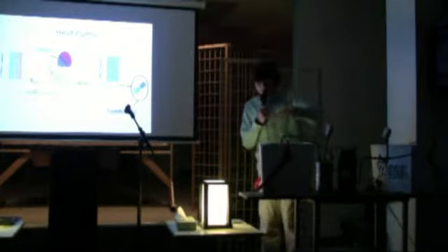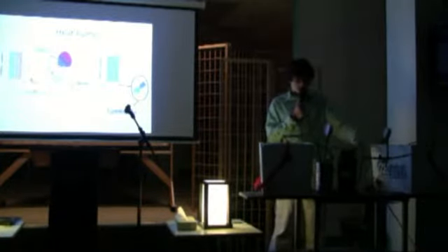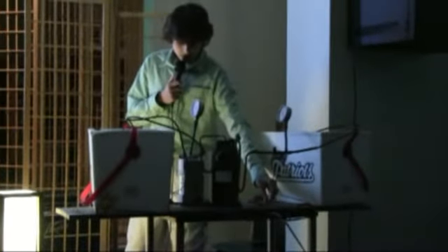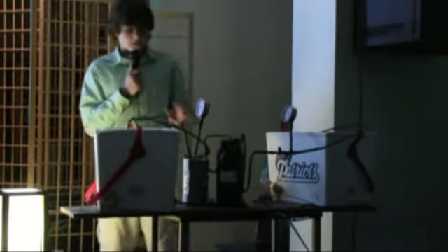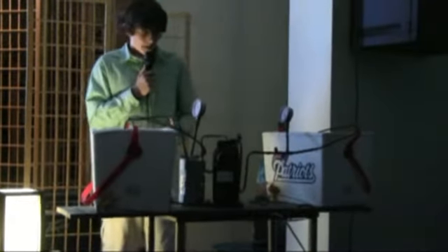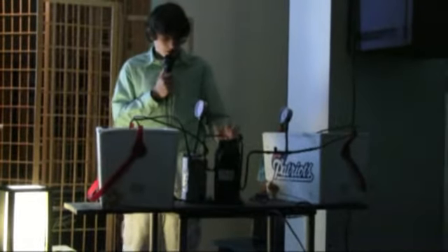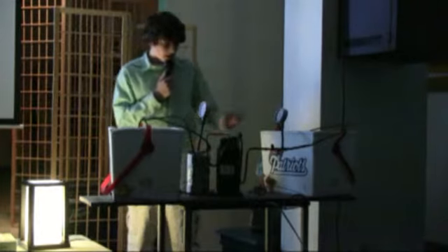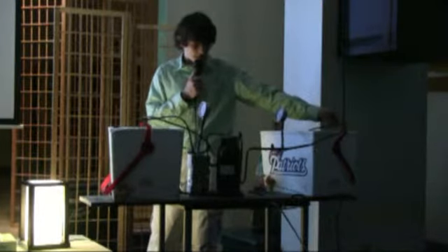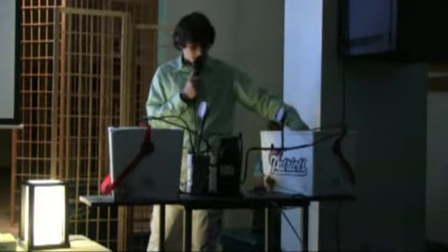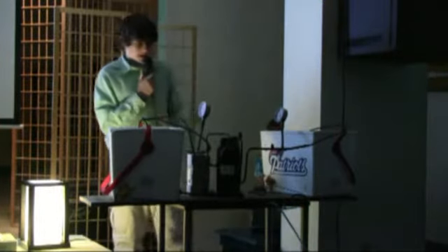So there's hot gas coming around through here, and the pipes get hot, so the pipes radiate heat into the air on this side. As it goes around, it goes through the expansion valve, which is this. It's under pressure, but when it hits this, the pressure gets released, it expands, and it starts to change state. When it changes state, it needs a little more heat to boil. So the heat is getting sucked out of the air and used so the gas can change state, which makes this area cold, and then it goes back to the compressor and repeats the cycle.